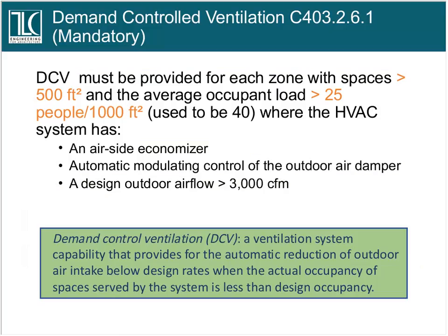So it used to be that any space that had more than 40 people per 1,000 square feet and was over 500 square feet, you would have to do demand control ventilation. In other words, modulate the amount of fresh air that goes into the space in response to the number of people that are in it. That number has gone down significantly. It's down to 25 people per 1,000 square feet. This essentially means every classroom and conference room and break room now has a mandatory requirement for demand control ventilation, unless you have those exceptions.